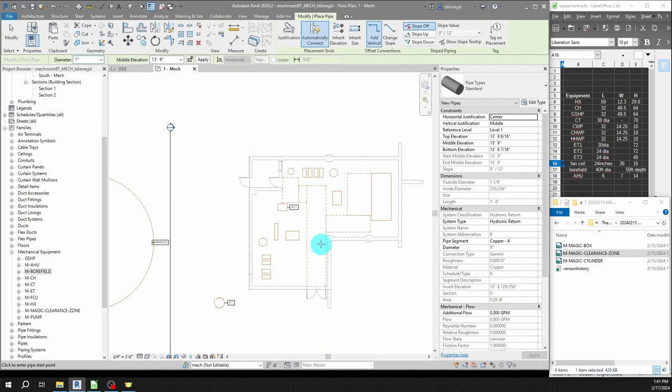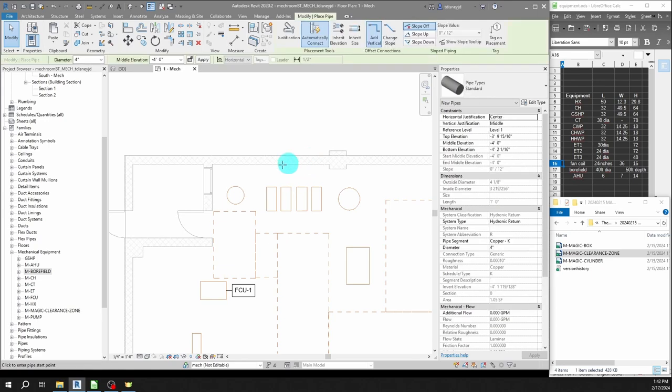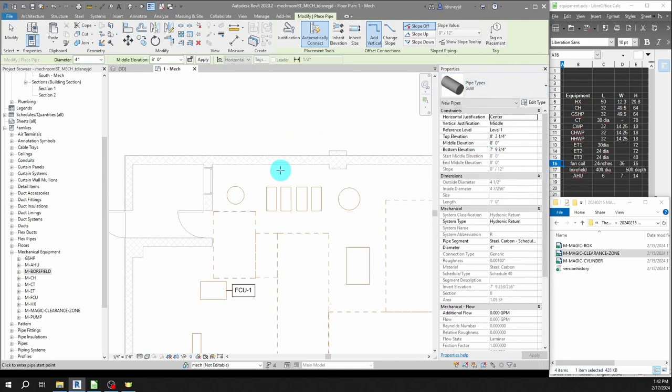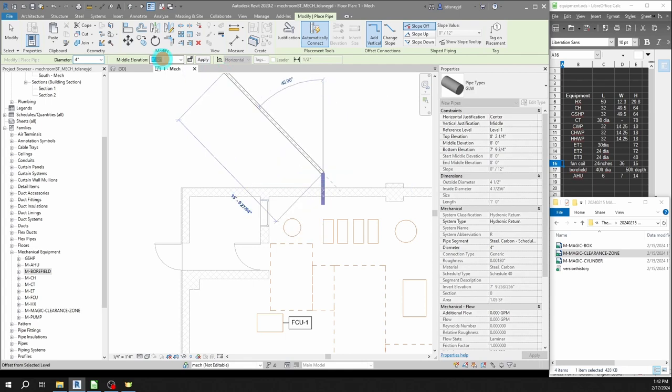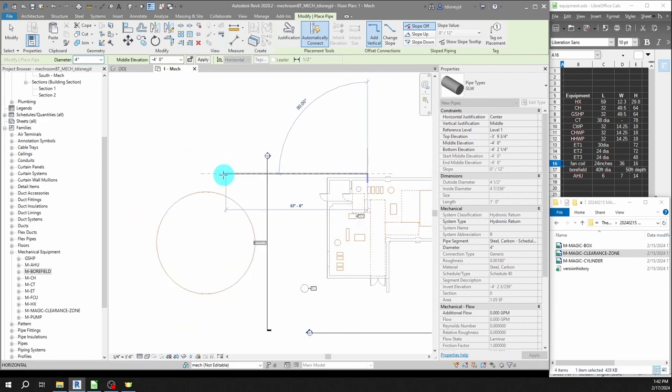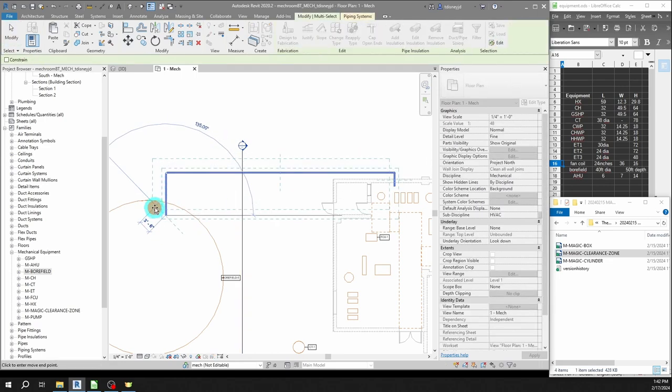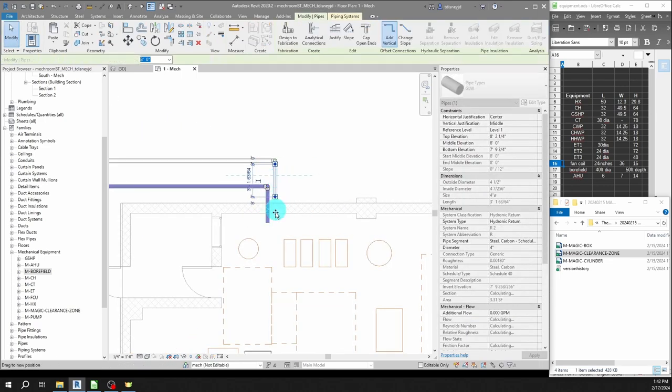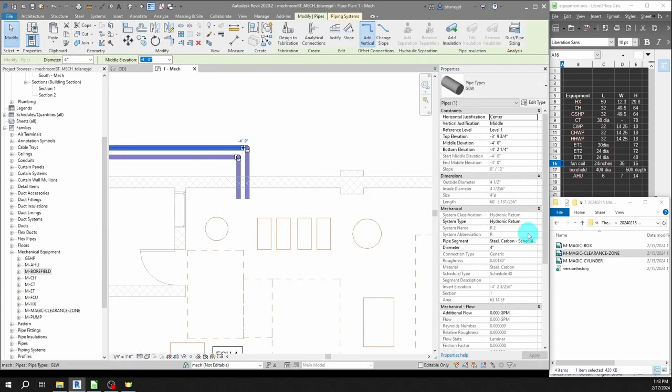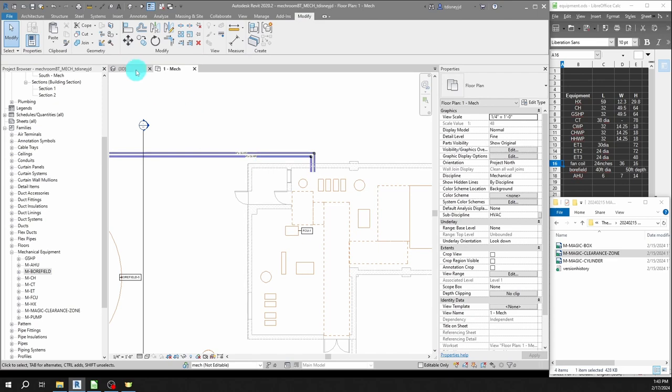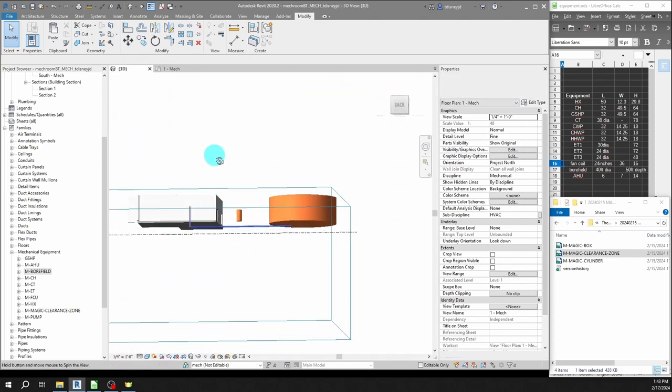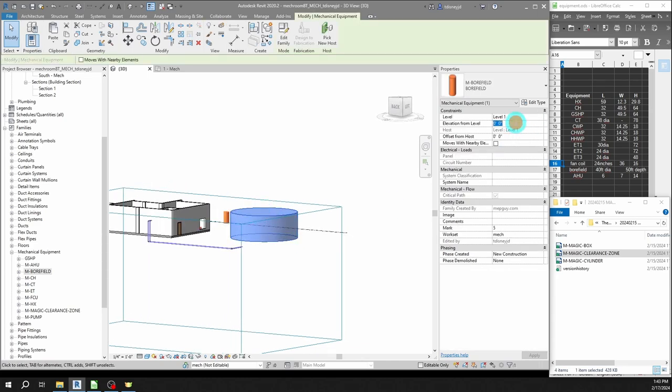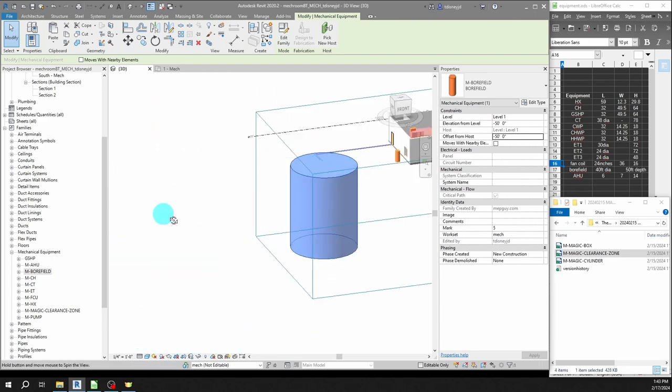What I'm going to do is show major distribution in and out of this space. I'm going to start with ground loop piping - four inch diameter. I'm going to start about eight feet and choose my ground loop water and start high, penetrate, go low below grade. This is interesting from a coordination perspective - civil might have something to say about this. Let me give it a check in 3D, it seems about right. Oh that's not right, that needs to be low, it needs to be negative 50 - it's a bore field, it goes down in the ground. That's why we check things in 3D, because we always make errors.